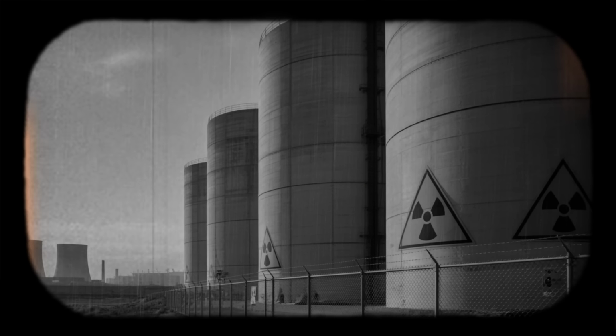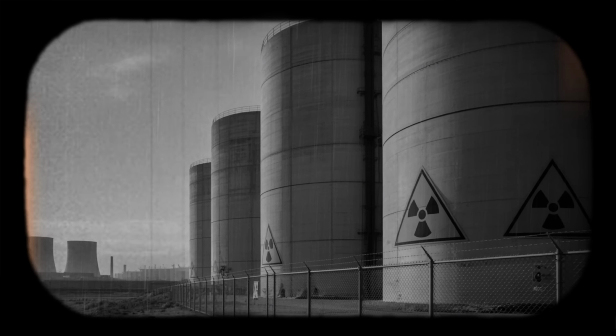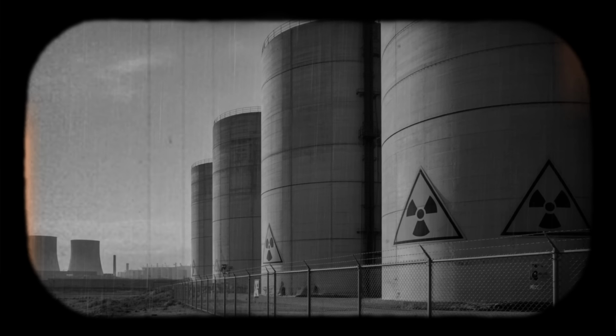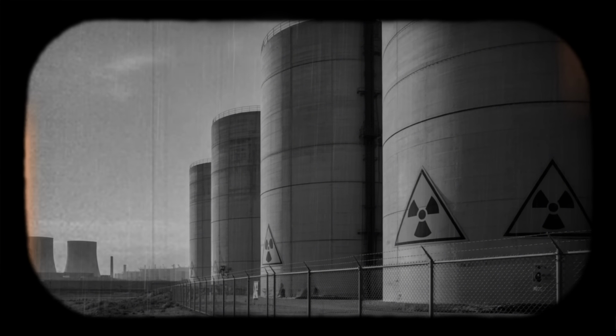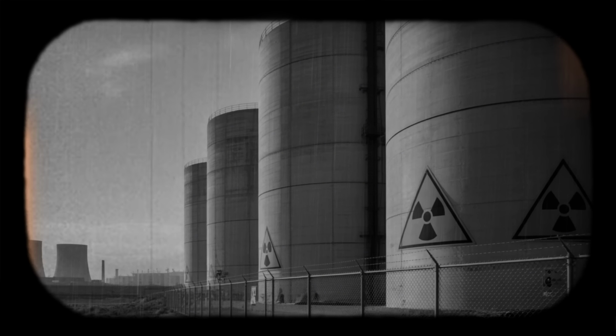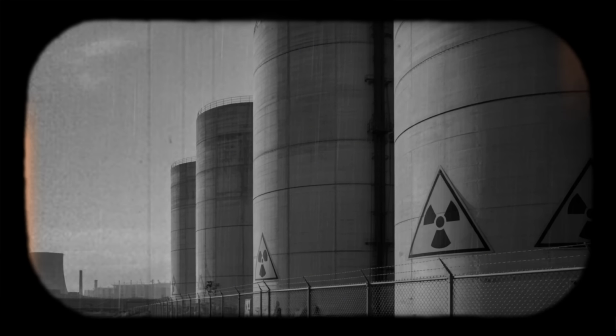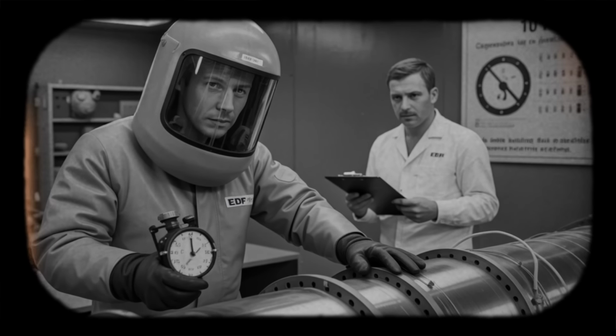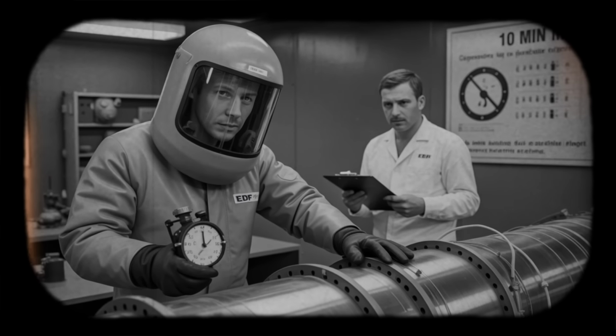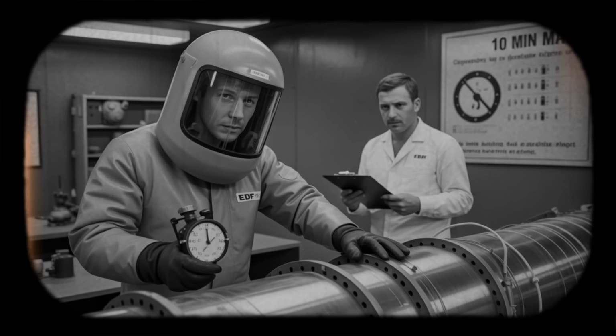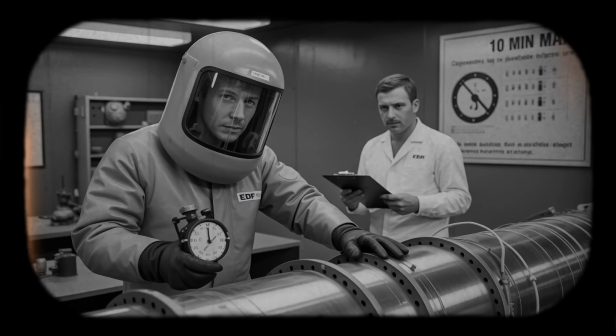Charging machine stops are not unprecedented. Some reflect genuine inconsistencies that require investigation. Others result from conservative logic that flags ambiguous conditions as errors. Distinguishing between the two often requires judgment. The schedule calls for completing the refueling campaign on time. Delays mean reduced availability, lost generation, economic penalty. The operator decides to override the automatic stop. Manual controls allow the sequence to resume.